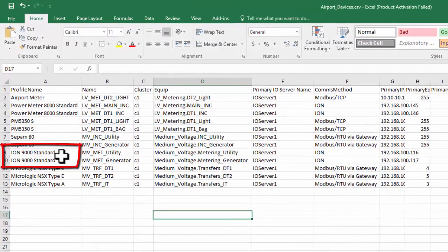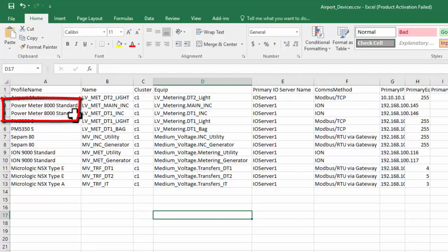In Schneider Electric terms, this means an ION 9000, PM 8000, or certain PM 5000 meters, as well as some older hardware. Secondly, having a capable meter may not be enough. The meter must be configured to capture waveforms on appropriate events. For ION meters specifically, this means setting a nominal voltage, but other meter lines will have similar requirements. Finally, we need a compatible communications protocol.